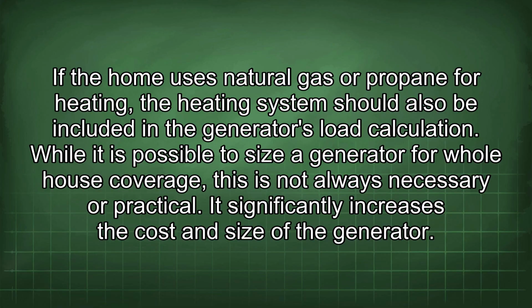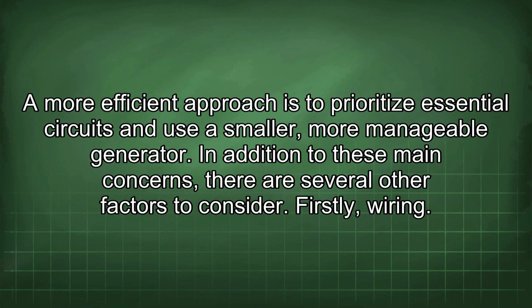load calculation. While it is possible to size a generator for whole house coverage, this is not always necessary or practical. It significantly increases the cost and size of the generator. A more efficient approach is to prioritize essential circuits and use a smaller, more manageable generator. In addition to these main concerns, there are several other factors to consider.